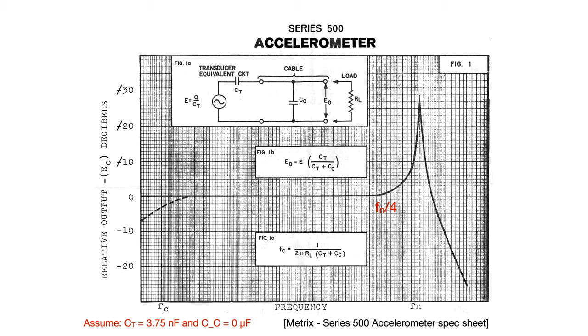At the low frequency end of this plot, the curve tends to curve downward. This is a result of the accelerometer serving as a high-pass filter and filtering out low frequencies due to the capacitance and the resistance of the load to which the accelerometer is attached.